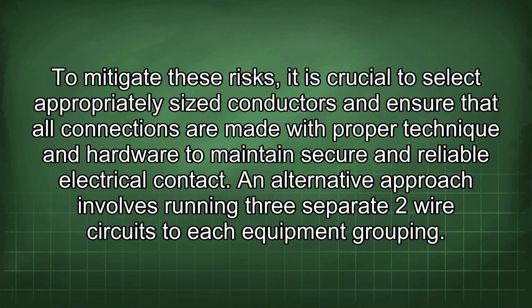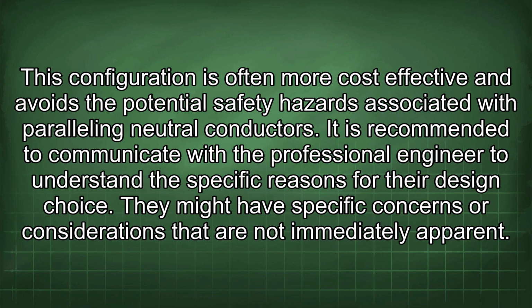An alternative approach involves running 3 separate 2-wire circuits to each equipment grouping. This configuration is often more cost-effective and avoids the potential safety hazards associated with paralleling neutral conductors. It is recommended to communicate with the professional engineer to understand the specific reasons for their design choice. They might have specific concerns or considerations that are not immediately apparent.